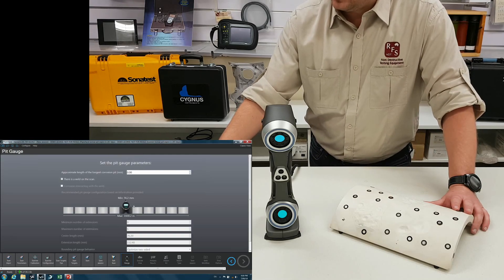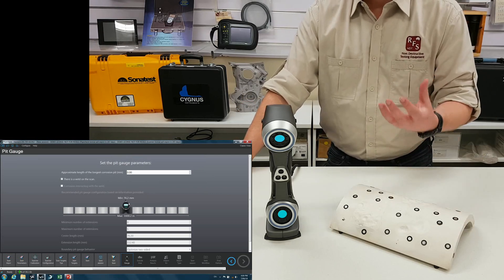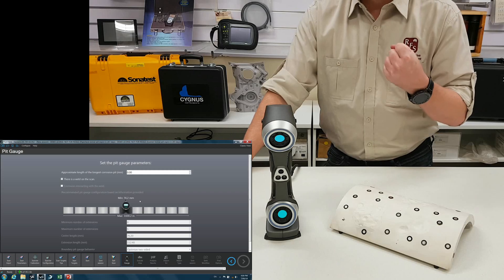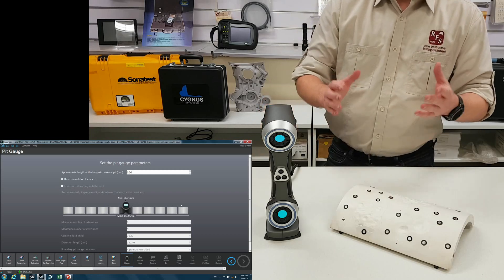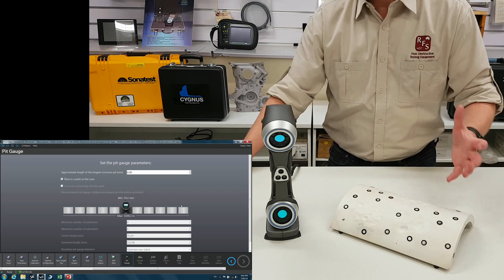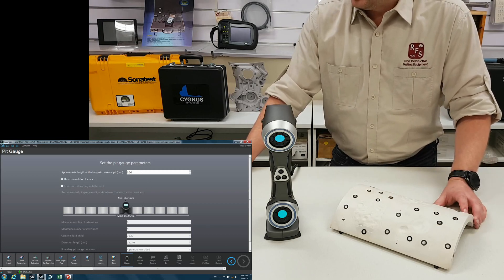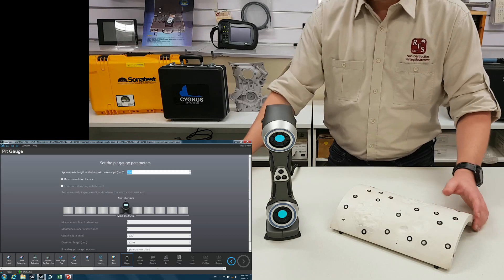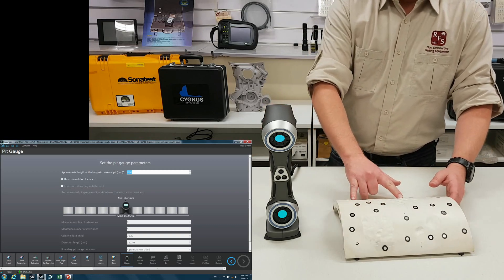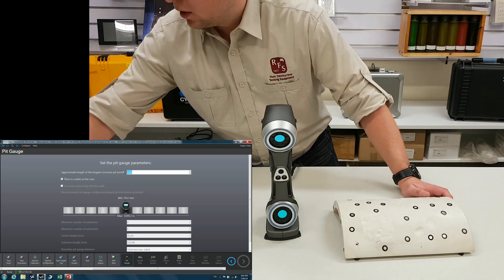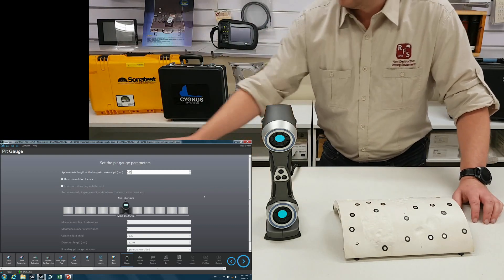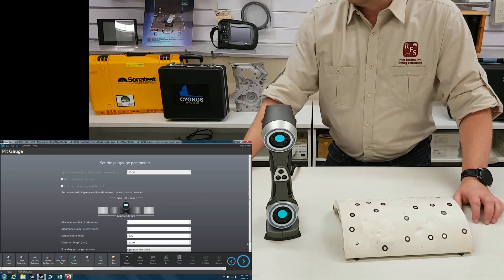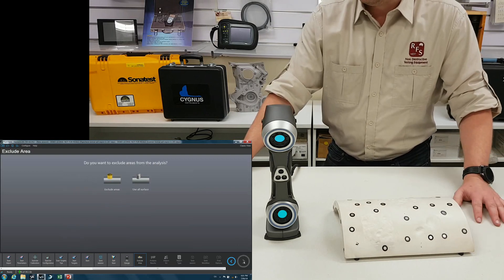So this is asking for parameters about your pit gauge. So it models a virtual pit gauge when it does an analysis. It's asking for things like how many extensions do you want to put on there, how long they are, everything you'd want to know. Approximate length of the longest bit of my corrosion, I'd say that's about 200 mil. So I'll put 200. And there we go. It's assumed what we need from that.